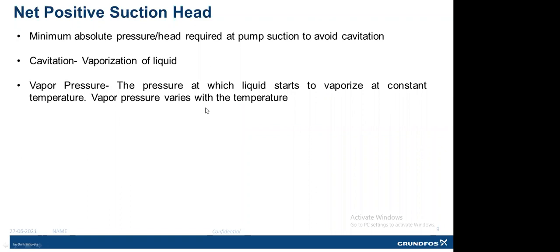And it's always recommended to operate the pump such that the NPSH available at site should always be greater than the NPSH required at that duty parameter. NPSH required is specified by the pump manufacturer in the pump datasheet as well as the pump curve, and it varies from duty point to duty point. That we'll see in the typical pump curve. But NPSH available at site should always be greater than the NPSH required by the pump, else the pump will start to vaporize.